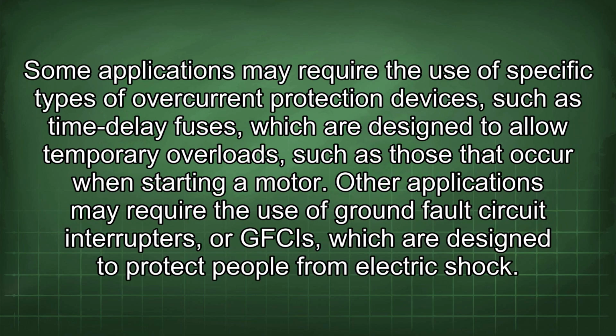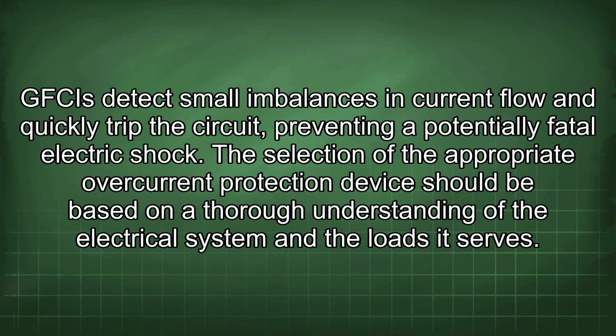Some applications may require the use of specific types of overcurrent protection devices, such as time delay fuses, which are designed to allow temporary overloads, such as those that occur when starting a motor. Other applications may require the use of ground fault circuit interrupters, or GFCIs, which are designed to protect people from electric shock. GFCIs detect small imbalances in current flow and quickly trip the circuit, preventing a potentially fatal electric shock.